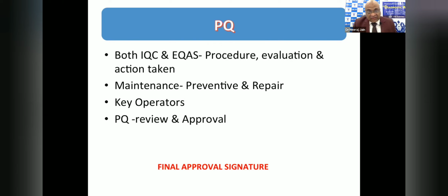This information shall be available close to the machine, and all these persons shall be trained and authorized to use that machine. This is your performance qualification. This is also reviewed and approved by some authorized person. So that way you are keeping all records of your machine as per IQ, OQ and PQ.